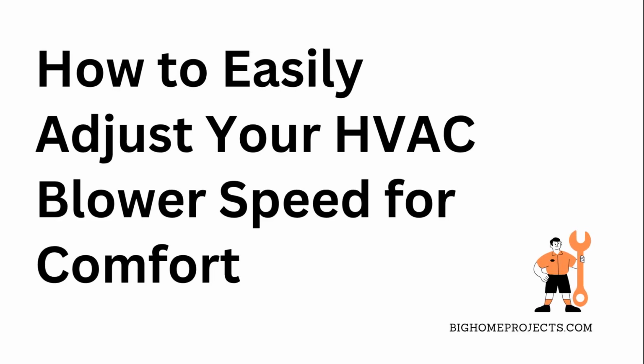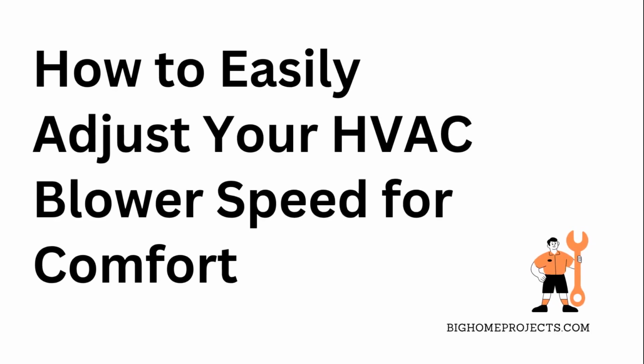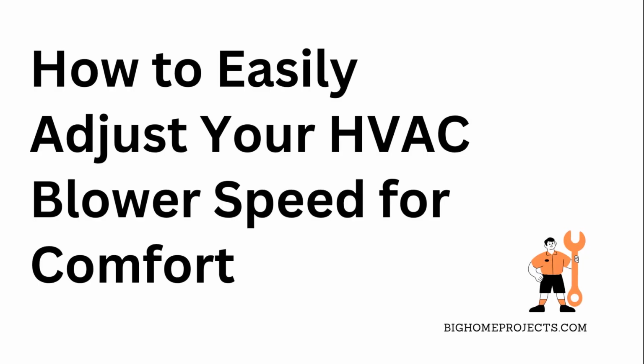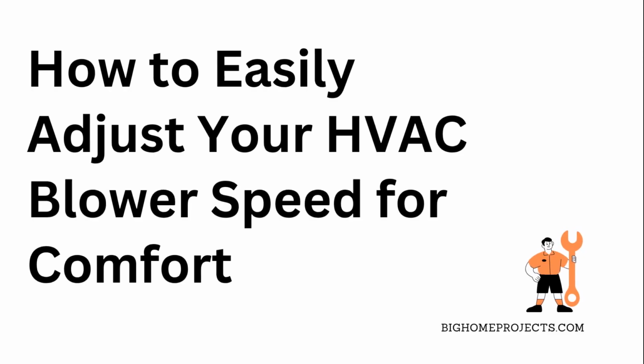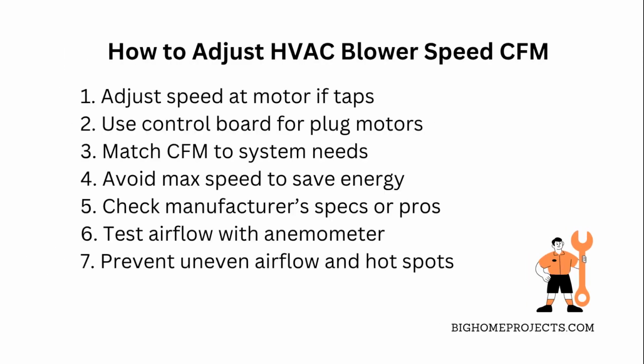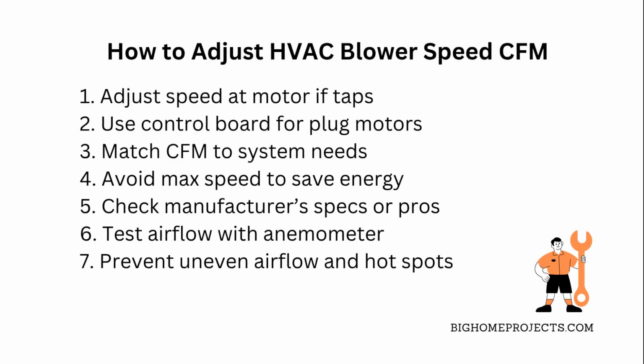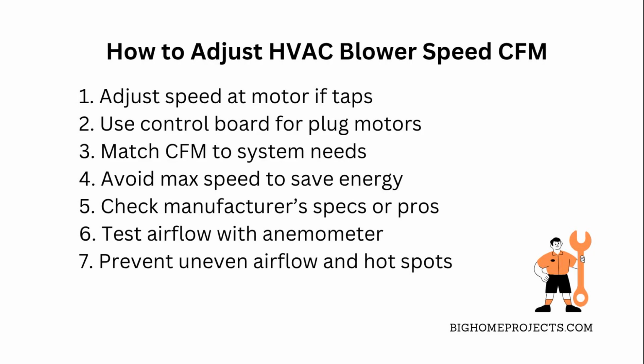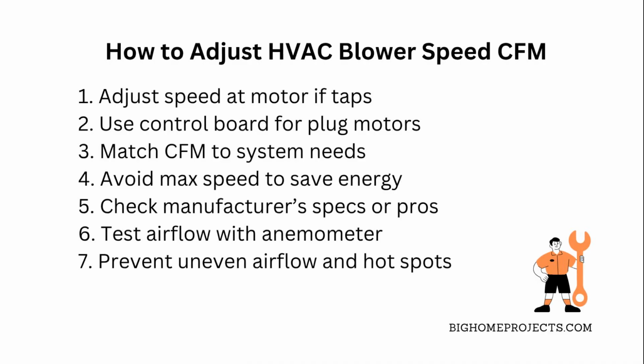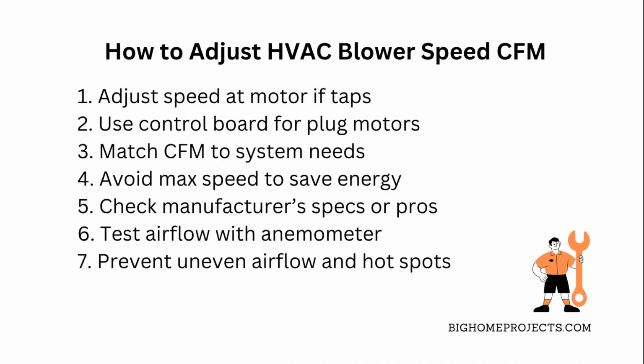Adjusting the blower speed CFM on your furnace and air conditioner can totally change how comfy your place feels and even save you some cash on energy bills. So, first off, if your supply air feels way too hot or cold compared to what it should be, that's a big clue your airflow might be off. Like, if the air coming out is super hot in heating mode or ice cold in cooling mode but the room still feels off, you probably got to tweak the blower speed.